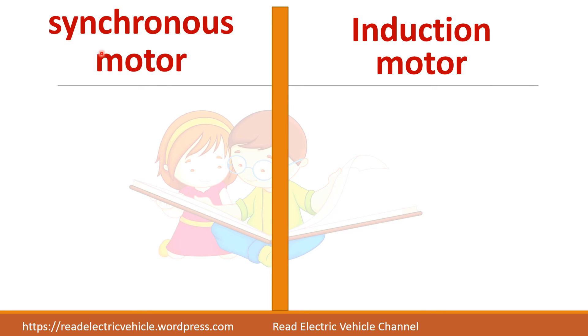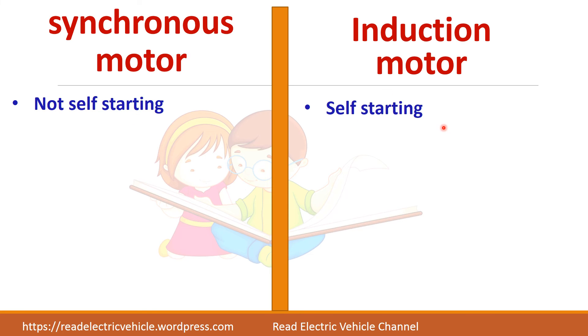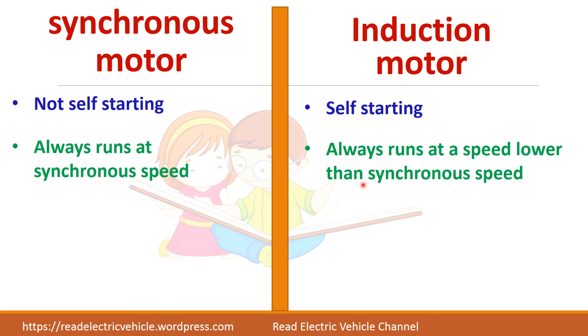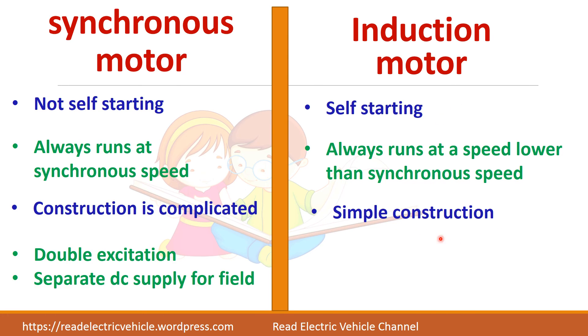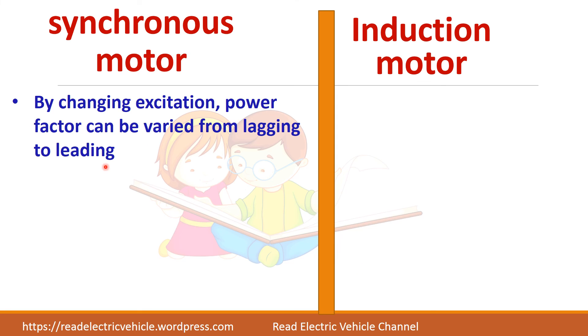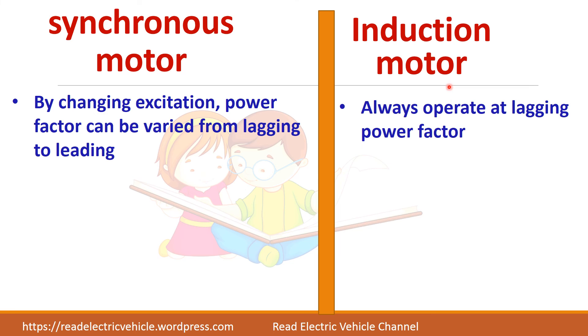Now we will see the difference between synchronous motor and induction motor. Both motors are AC motors. Synchronous motor is not a self-starting motor whereas induction motor is a self-starting motor. Synchronous motor always runs at synchronous speed while induction motor always runs at a speed lower than synchronous speed. Synchronous motor construction is complicated whereas induction motor has a very simple construction. Synchronous motor uses double excitation — AC supply for the stator and DC supply for the rotor — whereas for induction motor only the stator is given supply. By changing the excitation, the power factor can be varied from lagging to leading in the case of synchronous motor, but induction motor always operates at lagging power factor with no possibility to change it.